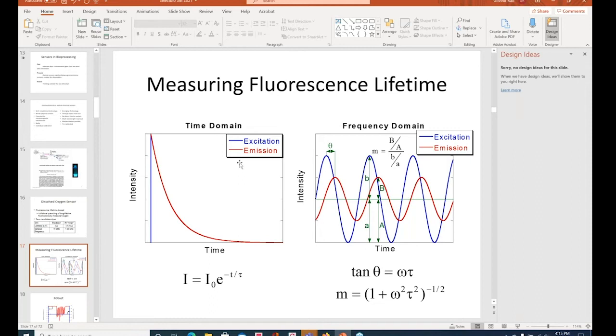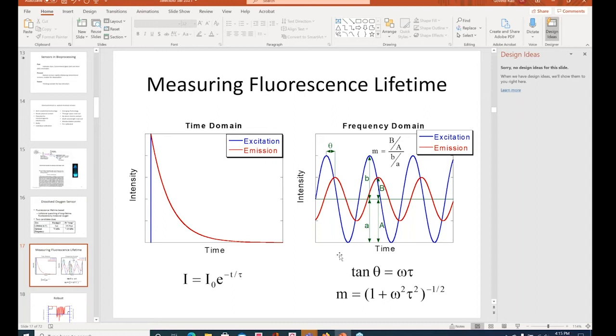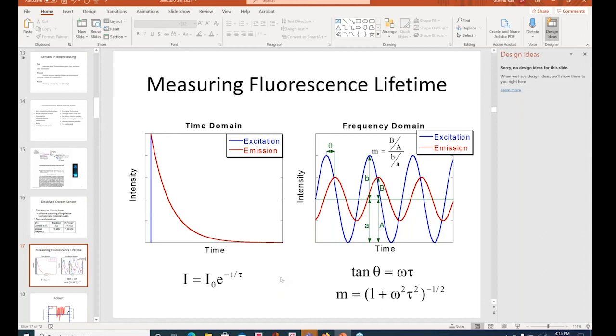This is kind of hard to measure with instrumentation because you need very complex gating and timing circuits. But it becomes trivial to do if you sinusoidally modulate your excitation. In other words, just make your excitation source flicker at a particular frequency. And then the emission that comes back comes with a phase shift that becomes very easy to measure. And this then becomes the basis of the oxygen sensor. Because what happens is oxygen quenches the fluorophore to a different degree. And by simply measuring this phase angle change, you're able to figure out what the oxygen level is. You can use very low cost electronics to do this. It's also a very robust measurement.